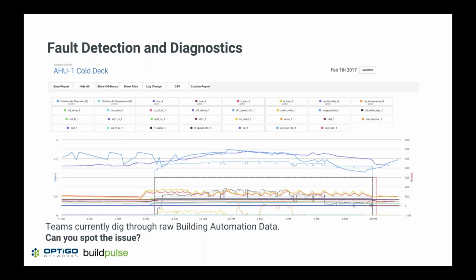Outside of just schedules, there's also sequence of operations and set points. A great question on the sequence of operations - often fault detection and diagnostics engines are supposed to audit for that. The trade-off being, if you have a building with 100 pieces of equipment, you'd have to have a guy sit there and manually inspect the data over and over again.